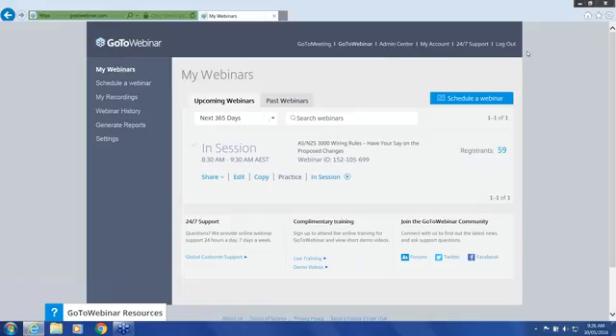At the moment, you can argue for lift-off panels you only need 0.6, and that's not consistent there. But with things open, you still have to apply the rule, 0.6 from the edges of doors and positions and things like that when they're open. So it's not particularly more damaging, it just tidies up some more clearances in larger switch rooms.